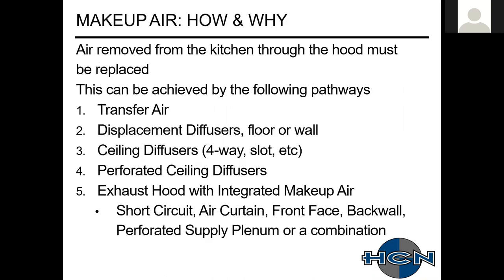So how and why do we introduce that makeup air into the kitchen where it's not going to affect the performance of the hood, and do it in an energy efficient manner? This can be achieved by the following pathways: transfer air, displacement diffusers, floor, wall, ceiling diffusers, perforated ceiling diffusers. And you can use perforated ceiling diffusers and displacement diffusers as ways to bring in transfer air as well, as if you were using a dedicated makeup air source.